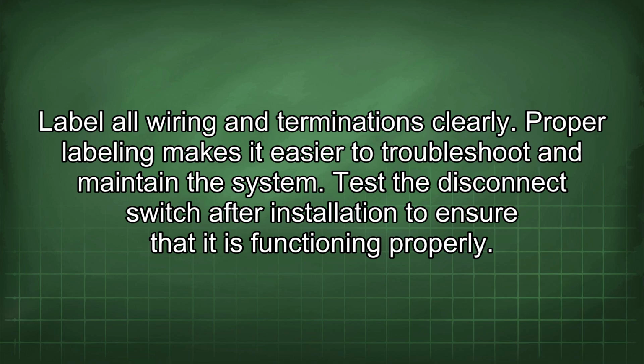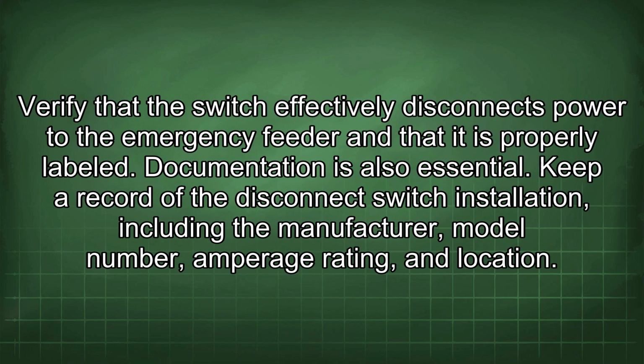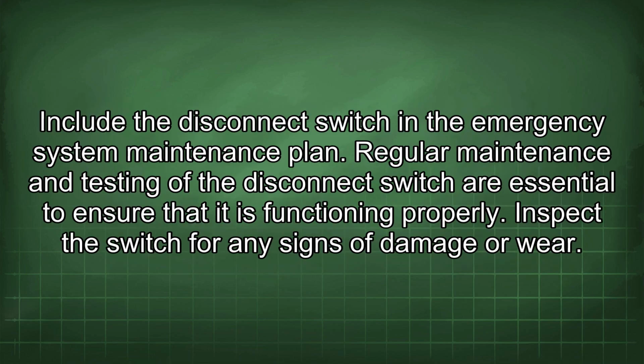Test the disconnect switch after installation to ensure that it is functioning properly. Verify that the switch effectively disconnects power to the emergency feeder and that it is properly labeled. Documentation is also essential. Keep a record of the disconnect switch installation, including the manufacturer, model number, amperage rating, and location. Include the disconnect switch in the emergency system maintenance plan.